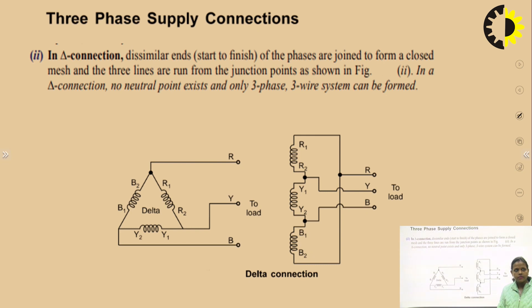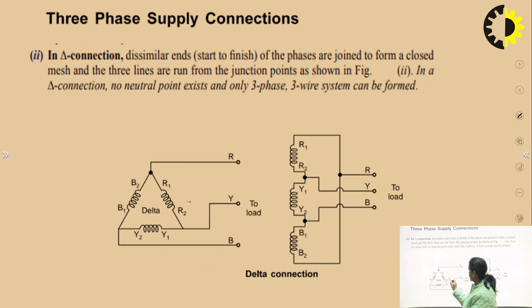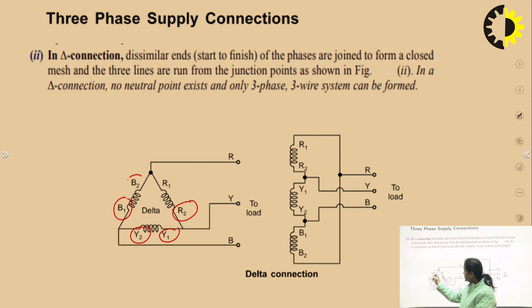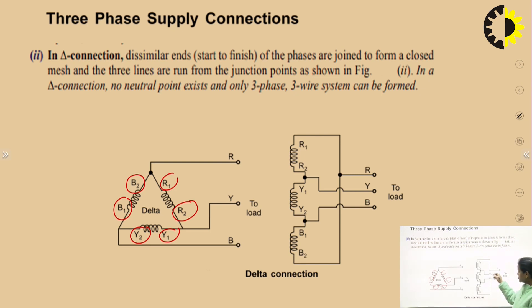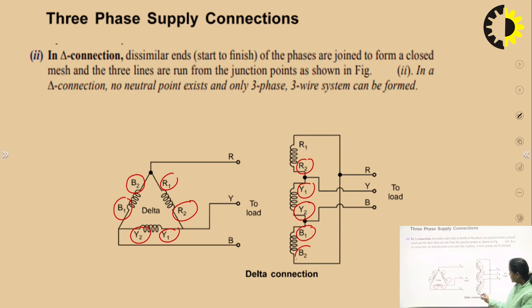In delta connection, the dissimilar ends of the phases are joined to form a closed mesh and three lines are run from the junction points. In a delta connection, no neutral point exists and only a three-phase three-wire system can be formed. The finishing end of one coil is connected to the starting end of the next — for example, R2 to Y1, Y2 to B1, and B2 to R1, forming the closed mesh.